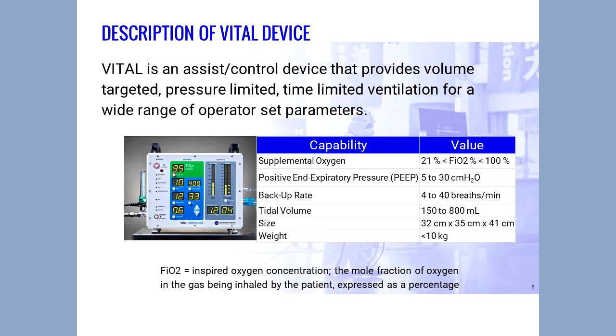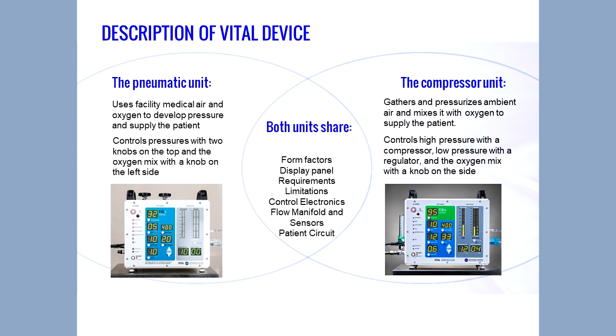So it's a reasonably small, moderately sized ventilator, and you see a picture here of one of the ventilators that we designed. We ended up picking and designing two different ventilators, and I'll go through this in a little more detail. Why not one? Why two different, fairly similar but slightly different ventilator designs? One we refer to as the pneumatic ventilator, and the other as a compressor ventilator. I'll describe briefly what each one does.